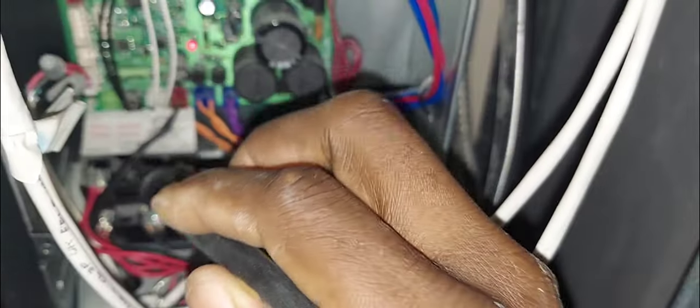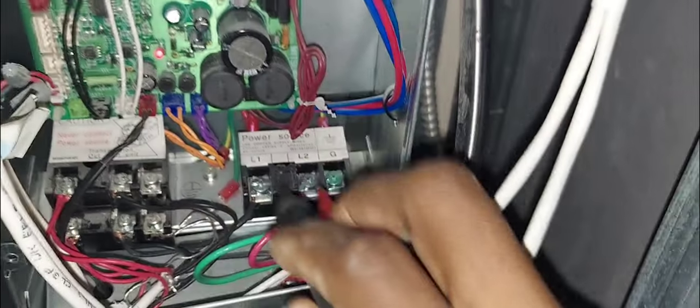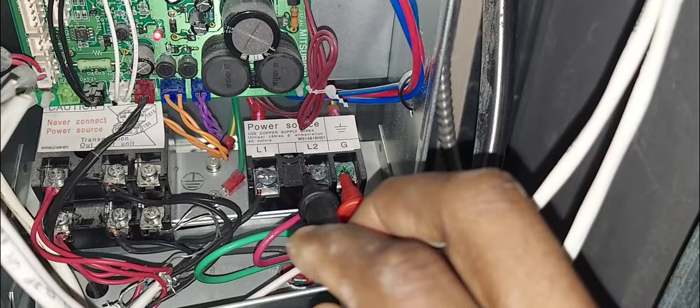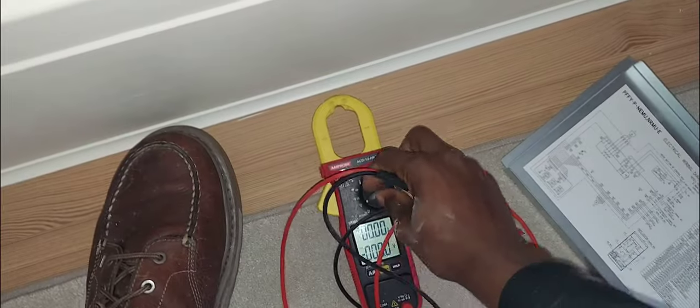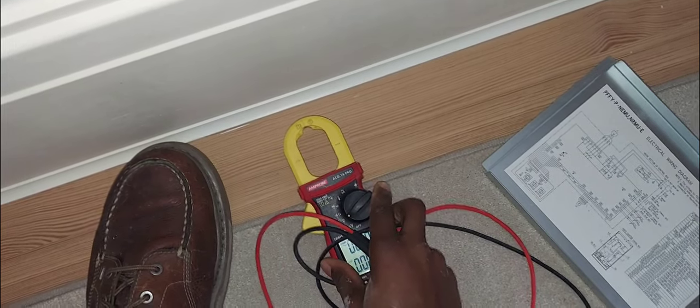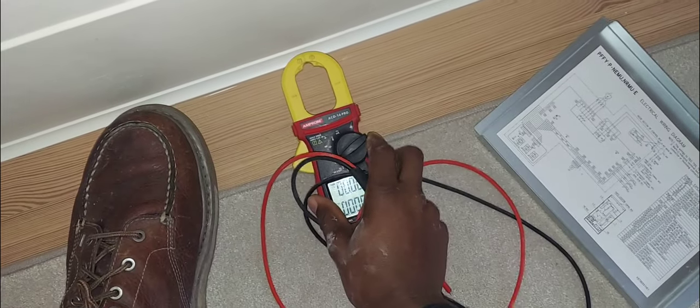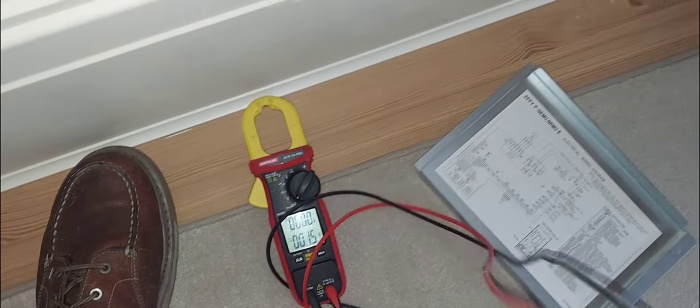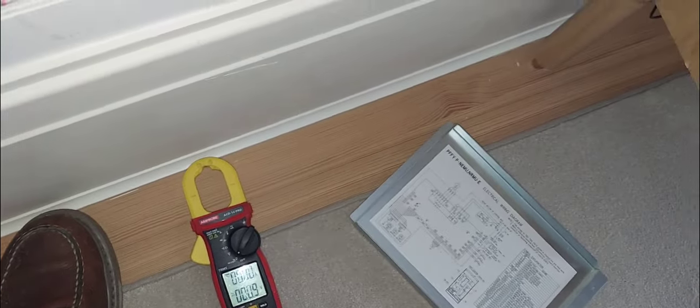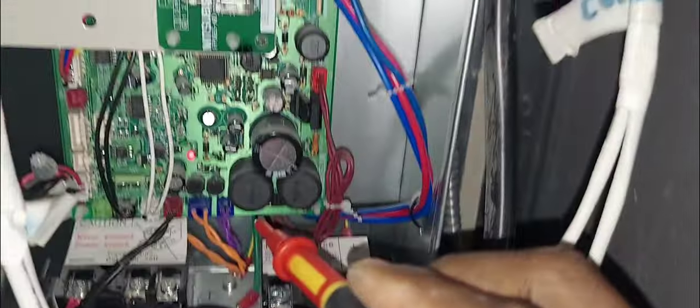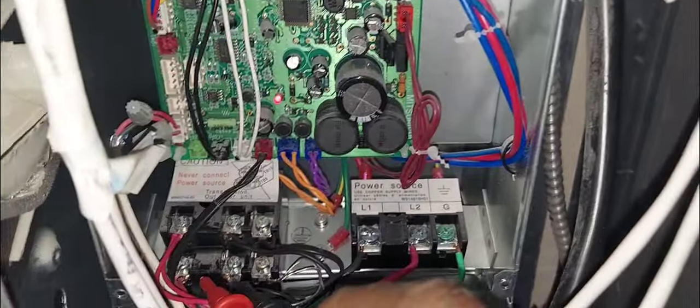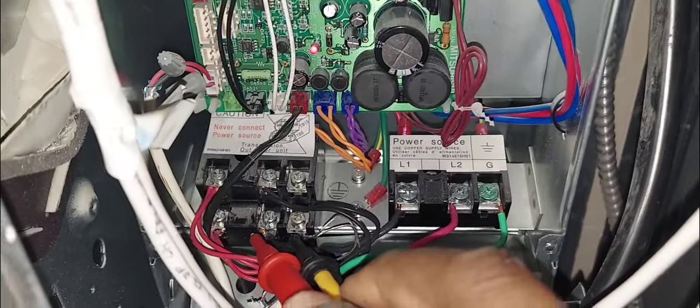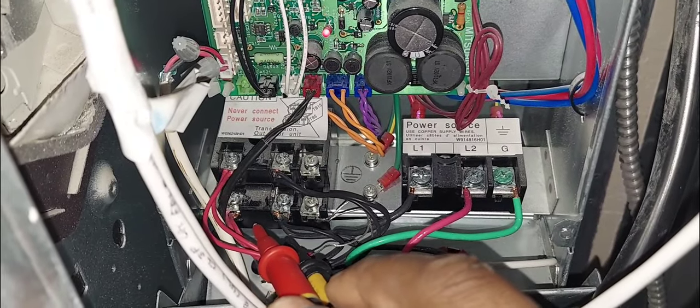Now guys, the power that feeds the outdoor unit is not to be confused with the part that feeds the indoor unit. The indoor unit, if it has power, it only sends power to the remote controller or the thermostat as you may. It doesn't send power to the communication or Mnet lines.